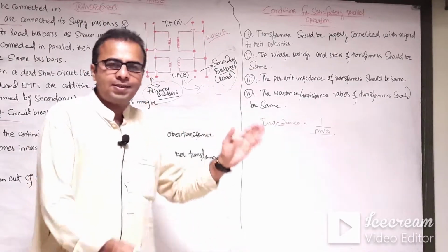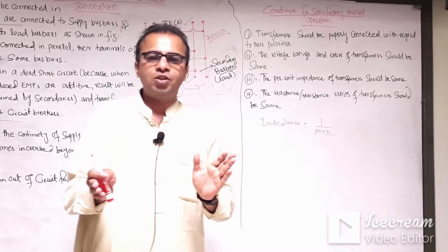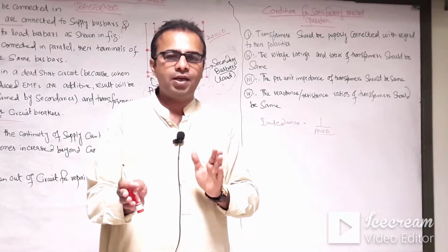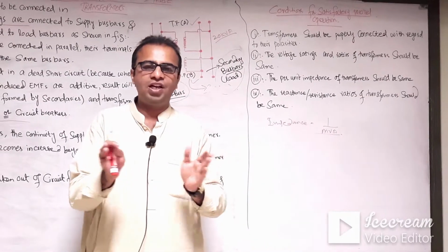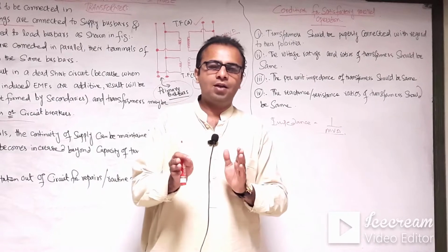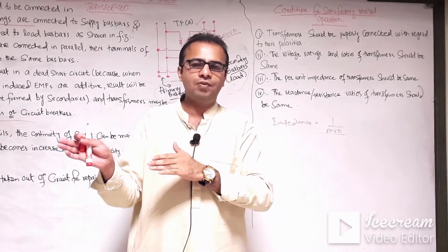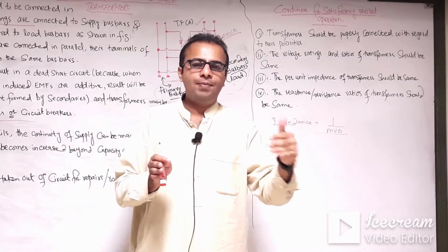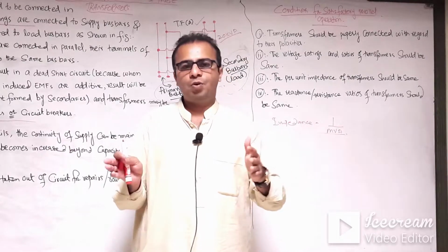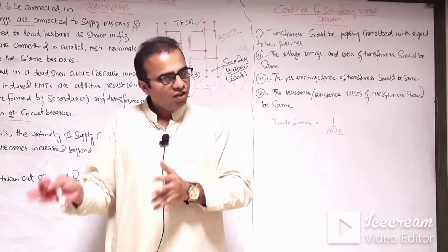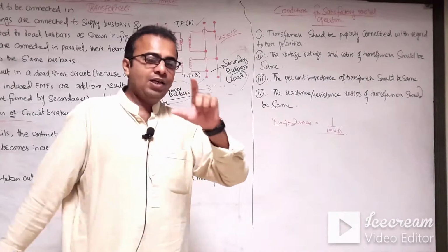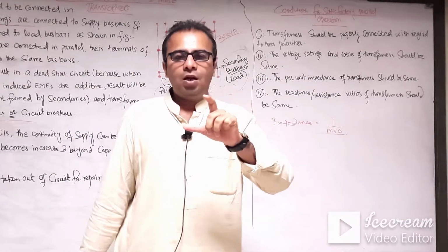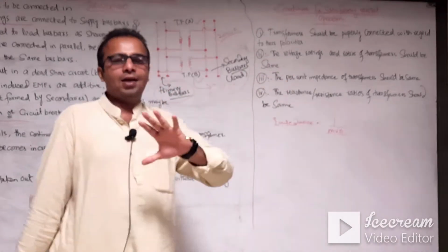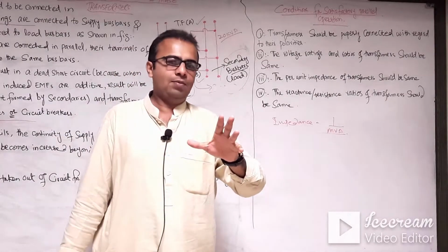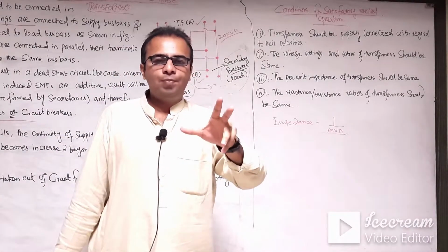If one transformer has the opposite polarity, the result will be a dead short circuit, or a wrong connection may be a dead short circuit, and the large short circuit current formed from the secondaries of the transformers may lead to damage of the transformers unless protected by circuit breakers or fuses. So the essential condition for satisfactory parallel operation is that the transformers are connected according to their polarities. Both transformers have the same polarity.